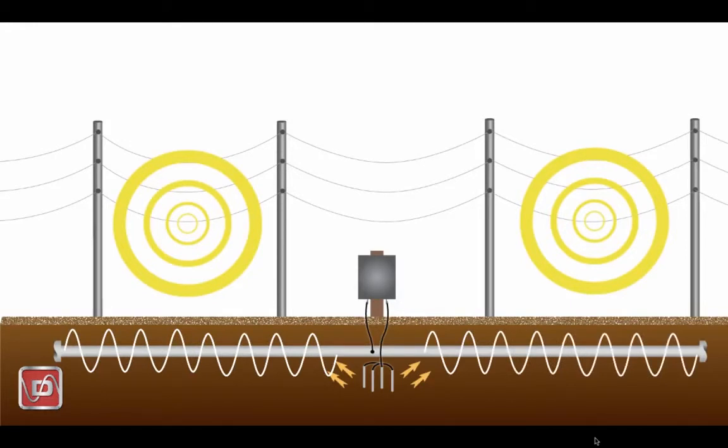Mitigating the induced AC is important both for personal safety issues and to prevent AC corrosion issues, and there are NACE standards that require mitigation of these induced voltages to certain safe levels. So we have to address these effects. Pipeline owners also have to address other temporary overvoltage conditions such as AC fault events and lightning strikes. We'll talk more about these later, but for now, let's install a continuous mitigation system using zinc ribbon to mitigate the induced AC.